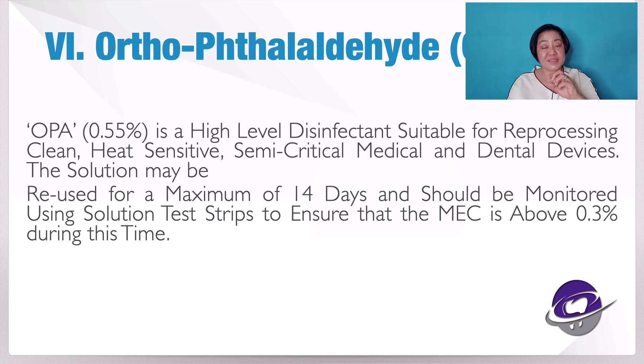Now, again, this is a good alternative for glutaraldehyde. However, the problem is that, like glutaraldehyde, you have to replace the solution and not use it beyond 30 days because it is not going to be effective. The advantage of this is that it has a wide pH range and it is not as irritating as glutaraldehyde.